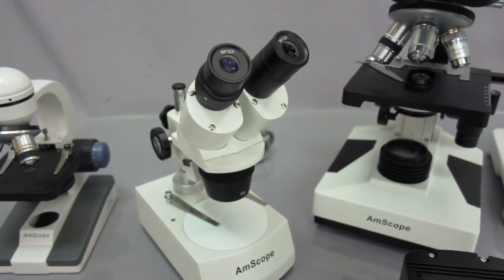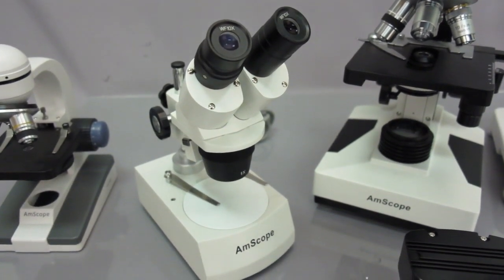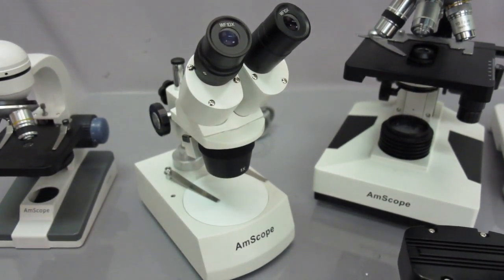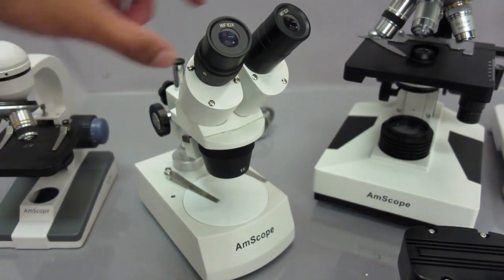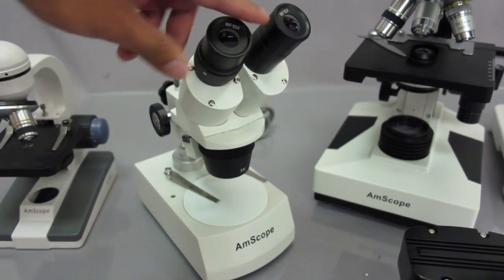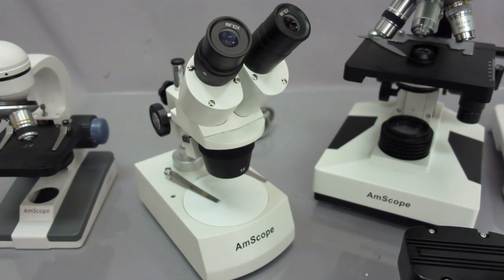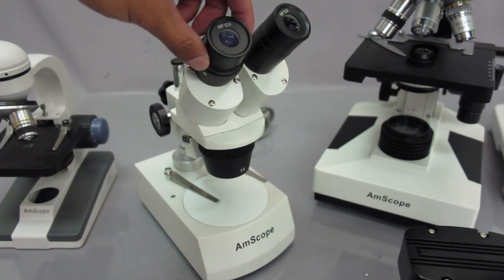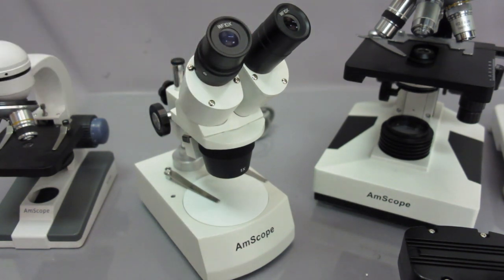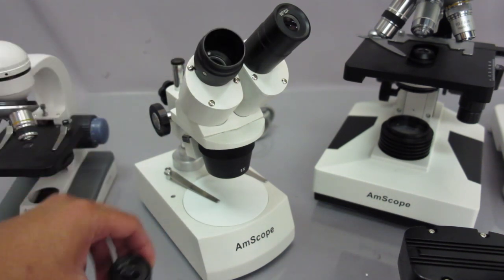And let's go ahead and try to mount the cameras onto one of our SC300 series. You'll notice that these microscopes are different because the eyepieces are bigger than 23 millimeters, which is usually the standard size. So these come at a standard size of 30.5 millimeters. And what you have to do is remove the eyepiece by removing a small screw that holds the eyepiece in place. So you could just remove the eyepiece like that.